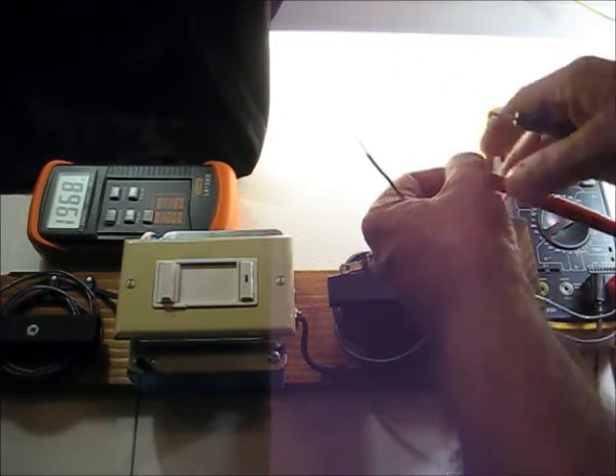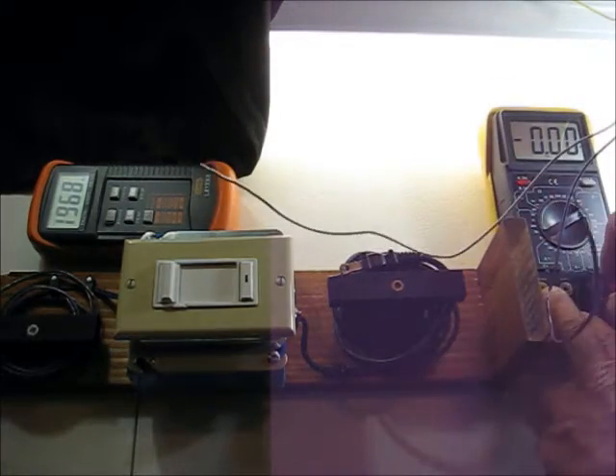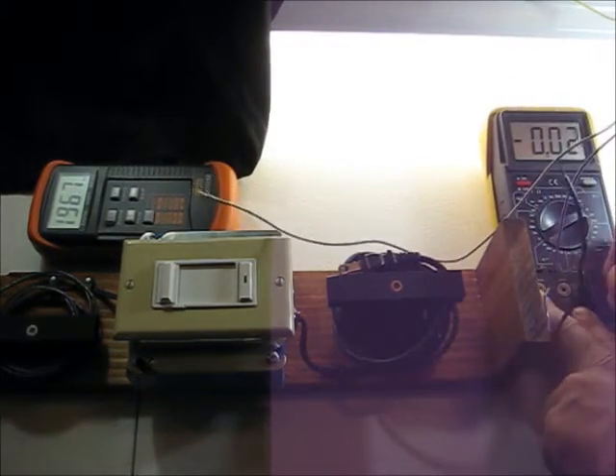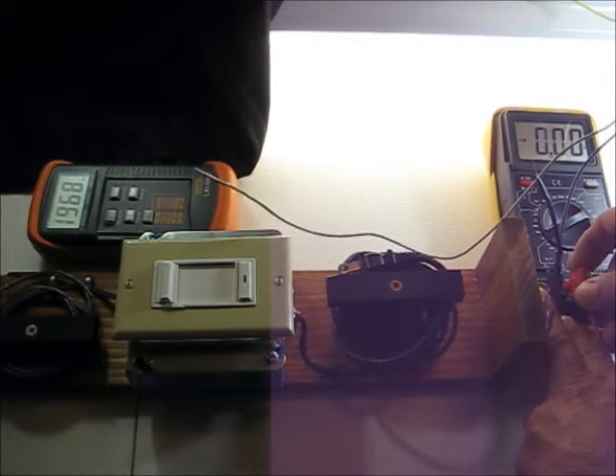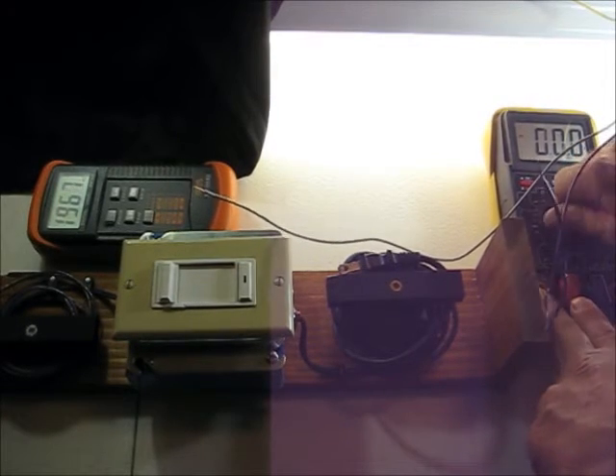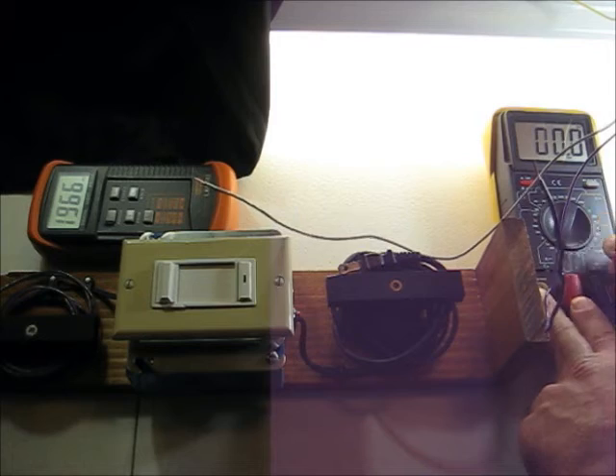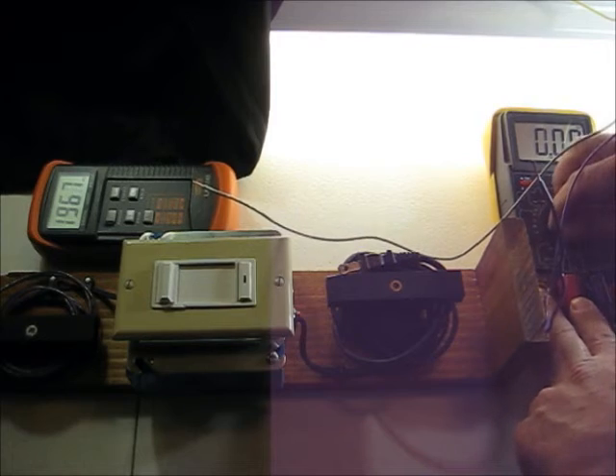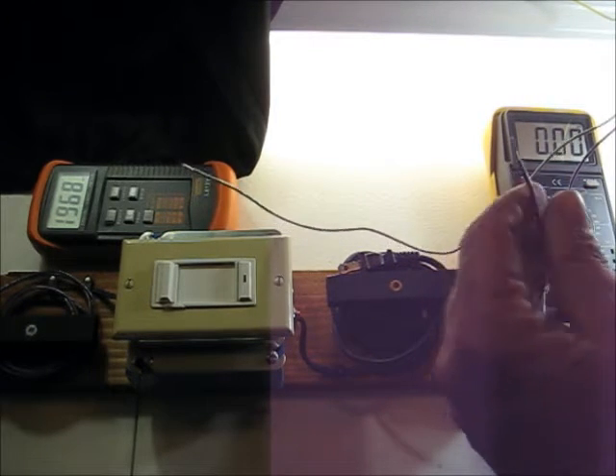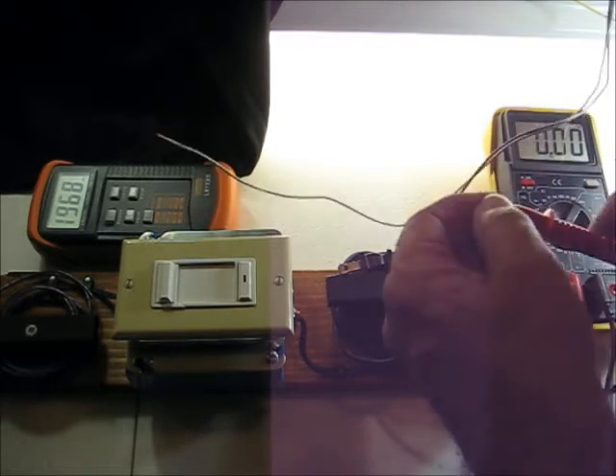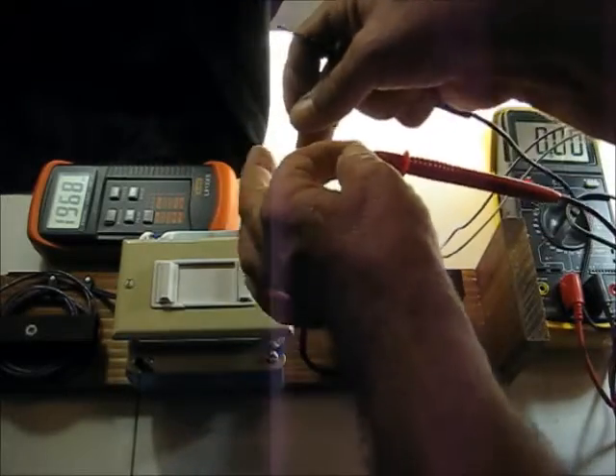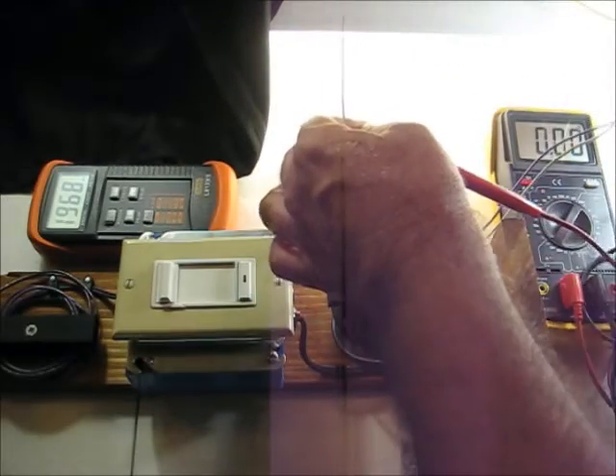I've got 13 and a quarter volts. The next thing you're going to want to do is check the current generation on your 0 to 10 volt control lines by shorting it through an ammeter. And remember, an ammeter is a direct short.